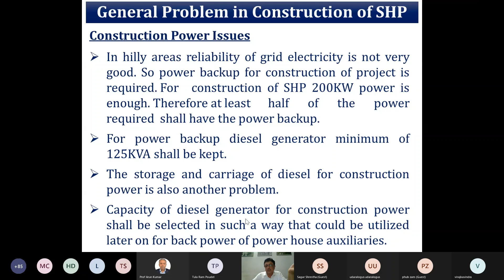We can select the capacity of the diesel generator for construction power in such a way that it can later be utilized for power backup of powerhouse auxiliaries, since every powerhouse requires power backup. So the generator used during construction activities can be used for auxiliary consumption later on, which will also save cost for the developer.